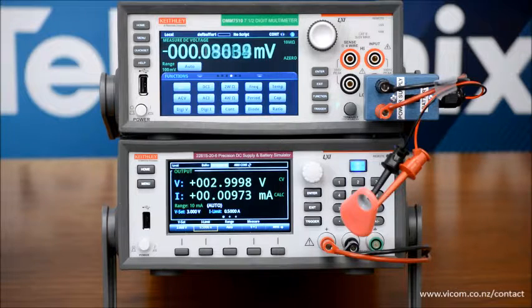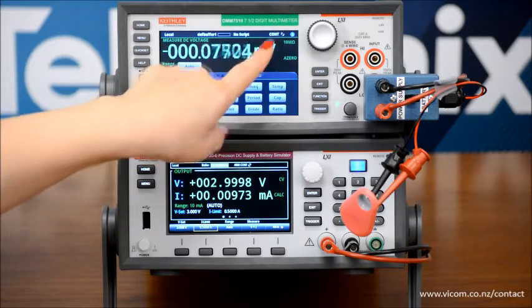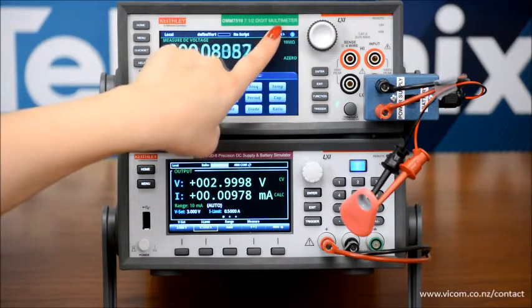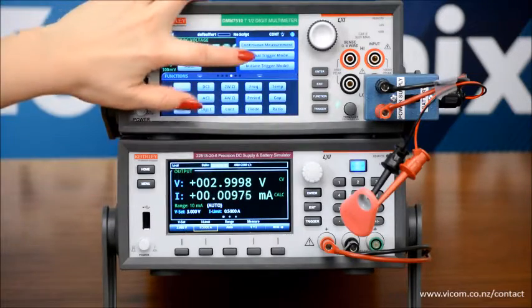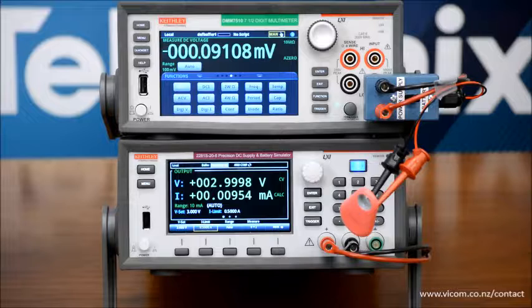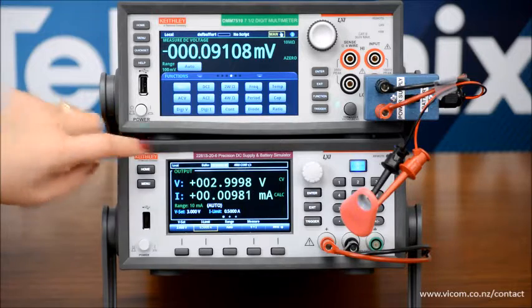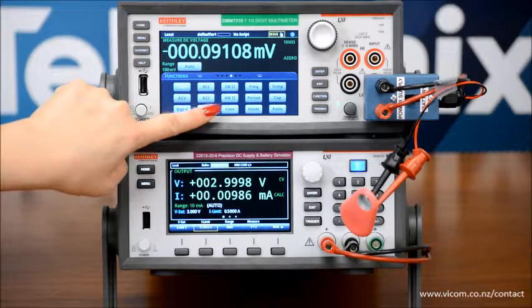Well, we'll do that on this DMM7510 graphical sampling DMM. Let's first pause the acquisition by pushing continuous and select manual mode, and that goes into the single trigger mode. Now I'm going to select DGI for digitized current.